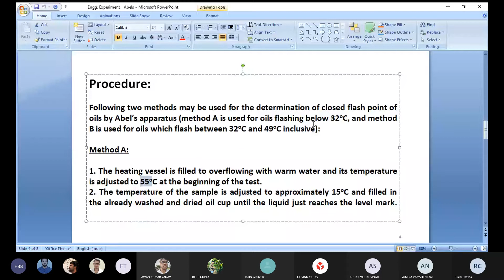So the temperature of the water bath is initially maintained at 55 degrees and the temperature of the oil will be maintained at 15 degrees. We are talking about the lower cases right now, the lower flash point cases. Then the oil cup is fitted with the cover. You will place the cover on it with the slide closed, and it is placed in the heating vessel. I told you that the oil cup can be dismounted from the entire apparatus. So you first remove it. It should be clean, washed and dried. Then you fill the oil in it. You place the cover on it and you mount it again on the heating vessel.